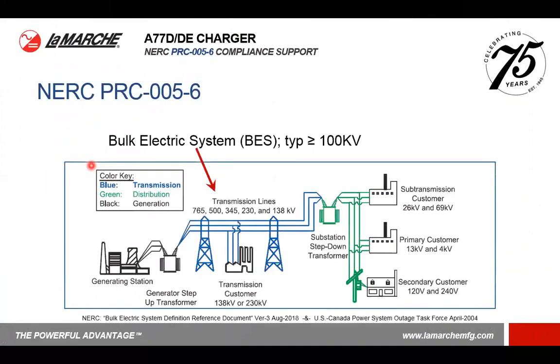Take a look at this diagram. The blue section in the middle shows the transmission system, which is in between the generating and ultimately the step-down substations and the customer. When the transmission voltage is at 100 kV or higher, essentially this is what applies to a bulk electric system. The complete definition of what a BES is actually within this document, the bulk electric system definition reference document. This is over 98 pages. But essentially the gist of it is if you're transmitting at 100 kV or higher, you're on the BES.